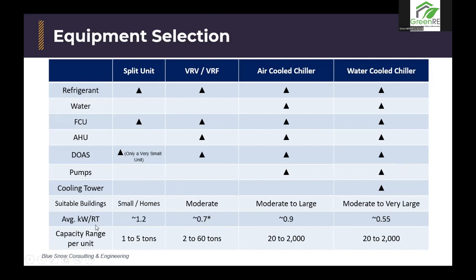And the average kilowatt per RT, also known as the efficiency by which we can rate the performance of the system, is 1.2 for the split units, 0.7 for VRV, 0.9 for air cooled, and 0.55 for water cooled. How we rate this is that the lower the number, the better the performance, or the higher the efficiency of the system. The next one is the capacity range. Split unit is between 1 to 5 tons. VRV VRF is 2 to 60 tons. And both air cooled and water cooled can range from 20 to 2,000 tons, or refrigerant RT.